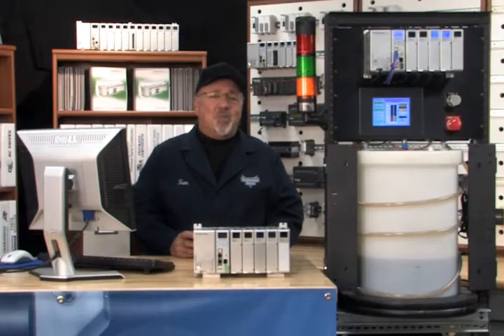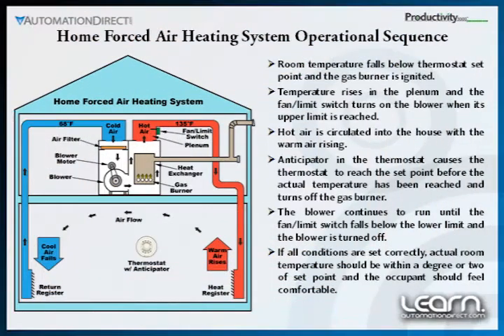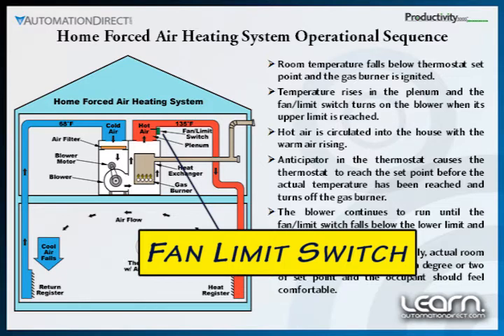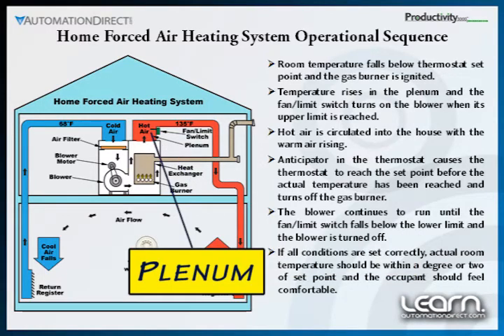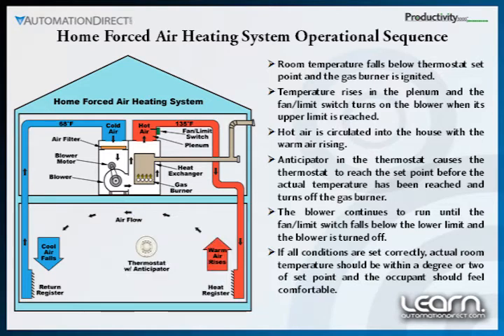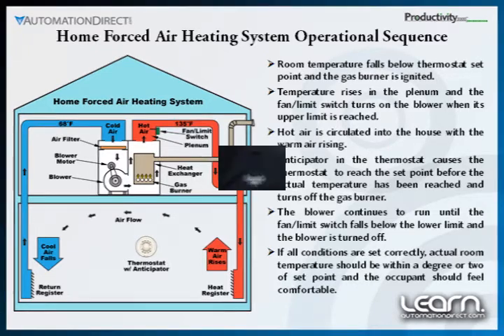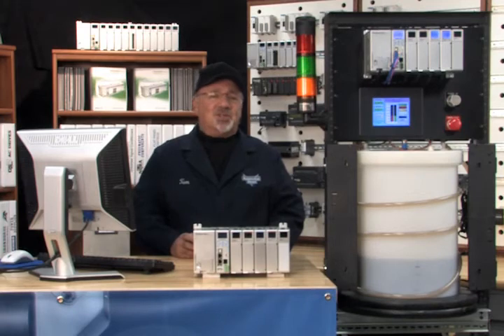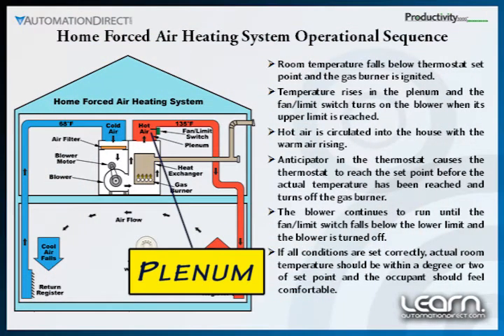To better understand the operation of the home heating system and get a better feel for what a PID loop controller can do, be aware that there is normally a fan limit control switch in the heating system. This allows the air in the plenum — a chamber above the heat source — to reach a certain temperature before the blower kicks on to force the heated air throughout the home. The fan limit switch prevents unpleasant cold air from being felt by the occupants and explains the lag between when the furnace's burner turns on and when the blower kicks on. Because of this condition, the system stores extra heat in the plenum, which would cause the room temperature to overshoot the desired temperature.